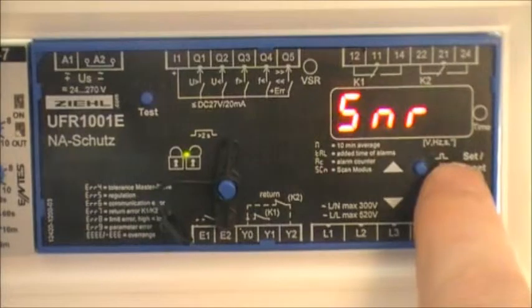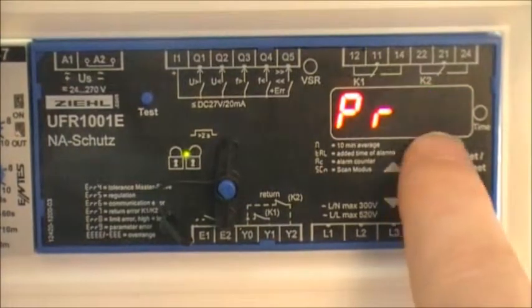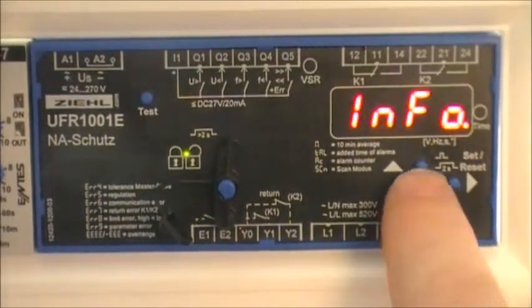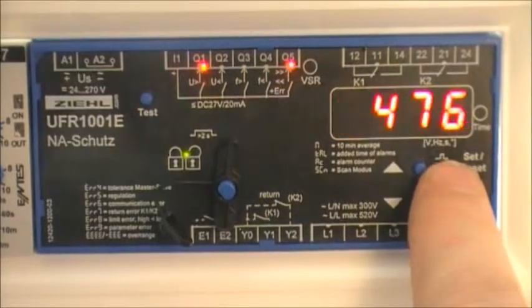So if we go up and we look at the info, go right, serial number, hours run, error messages, program 21 is now active. And if we go to the values for program 21 we will see the overvoltage should be 476 and there it is.